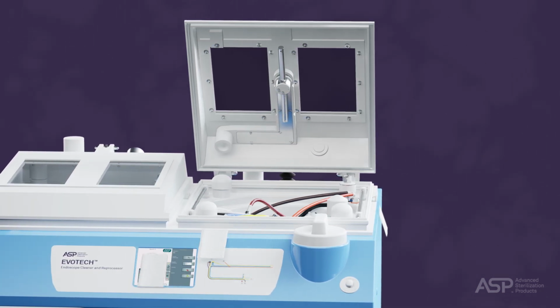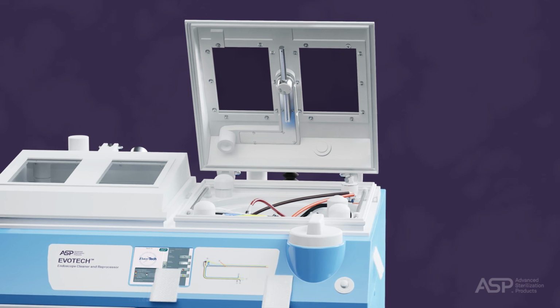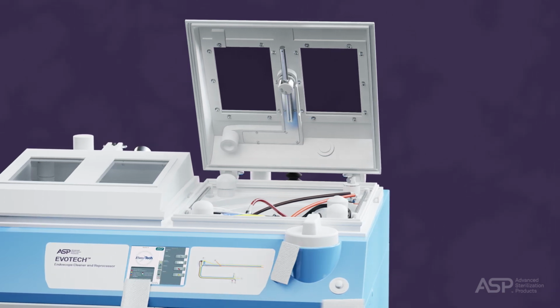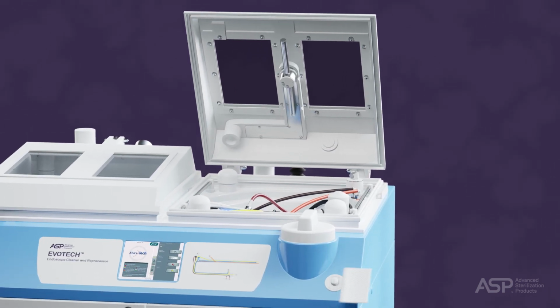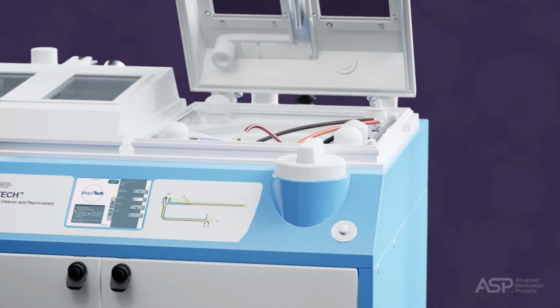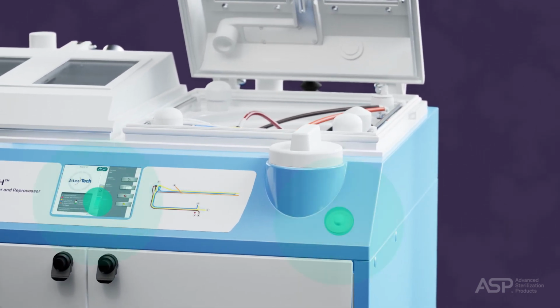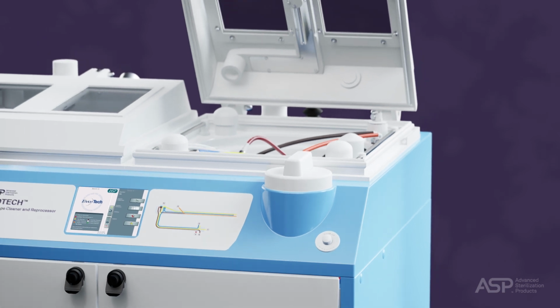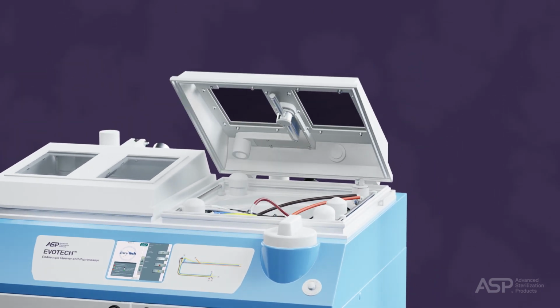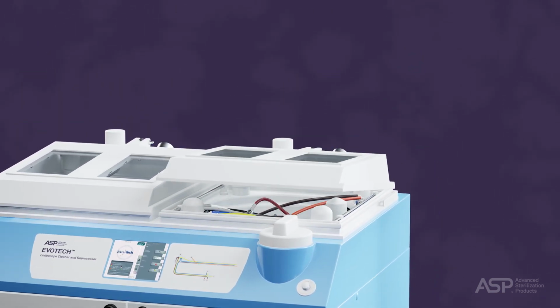Wipe any exterior areas of the EVOTECH ECR with alcohol-based wipes, as it may have come in contact with the dirty endoscope. Simultaneously touch the close lid button on the touchscreen and the close lid button on the front panel for the basin use. The lid should close completely. You will hear an audible sound as the lid seals.